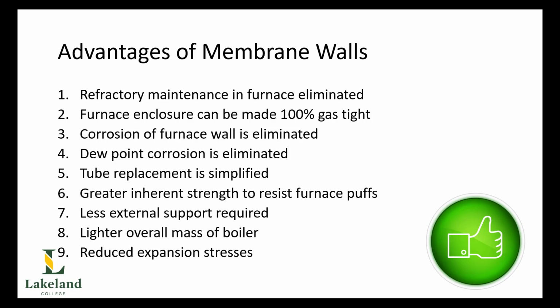Remember, forced draft furnaces are positive pressure. The next one is that the corrosion of the furnace wall is eliminated. Corrosion of the furnace wall is going to be by condensation typically of the gases inside of the furnace, and also dew point corrosion here is going to be eliminated as well by having it completely gas tight, as we'll have no air escaping into or out of our furnace itself. Fifth, tube replacement is simplified because tubes can be replaced by a technique called circumferential welding, and this means that entire sections of water walls do not need to be replaced in one go.